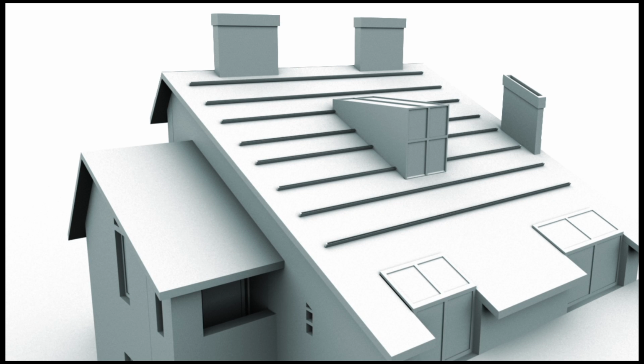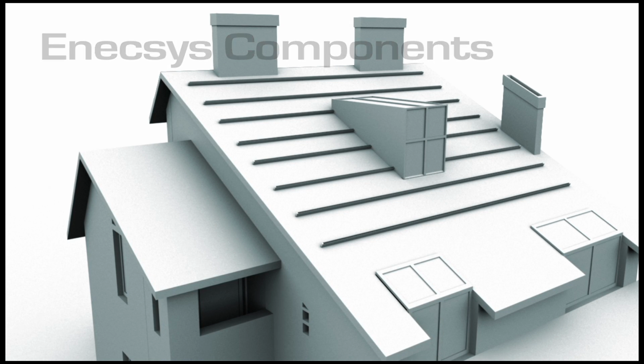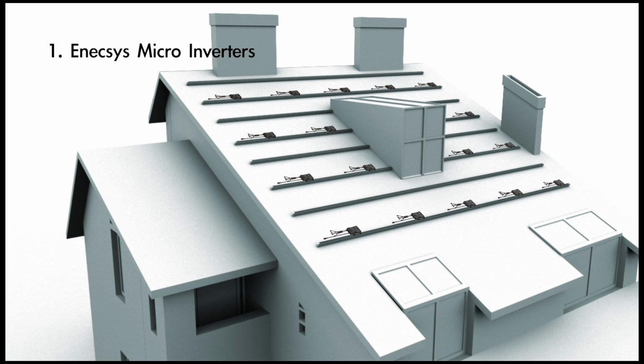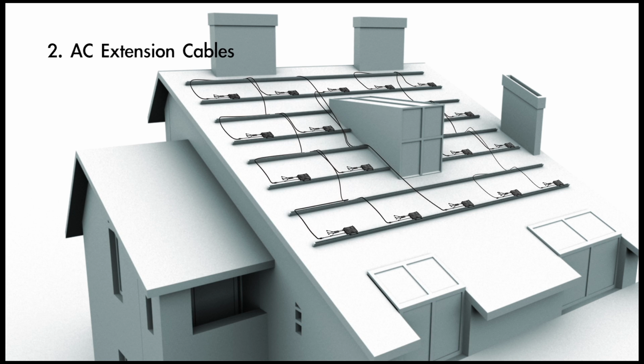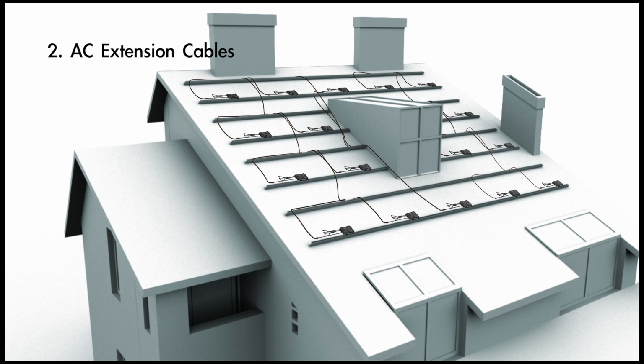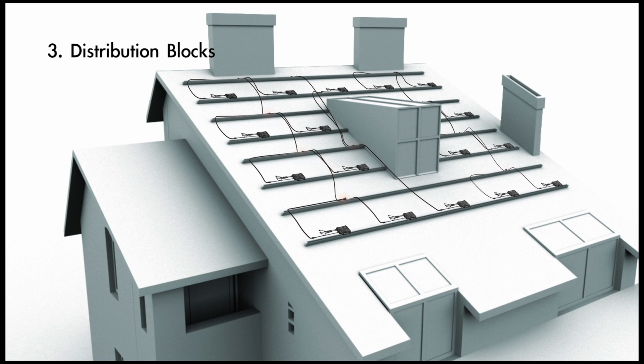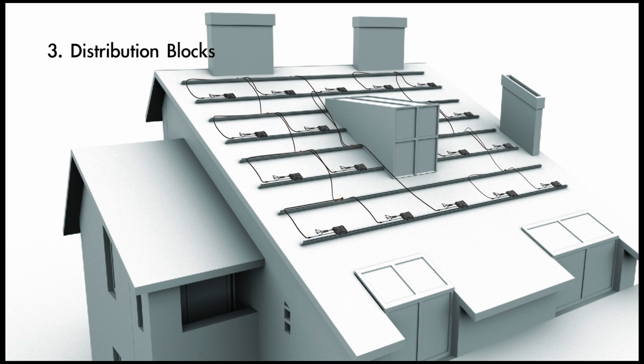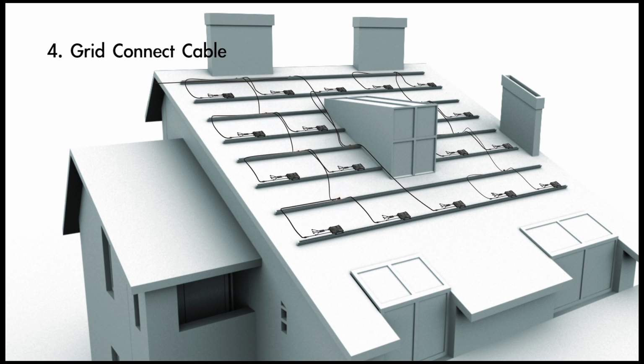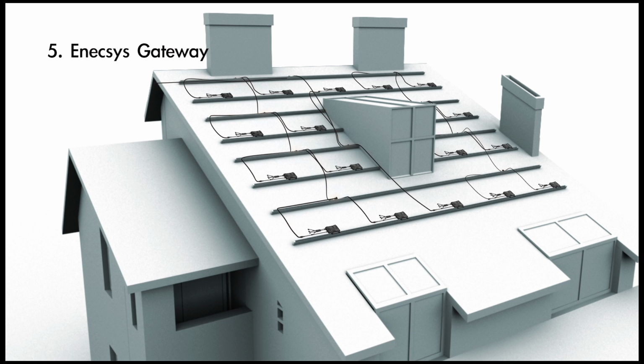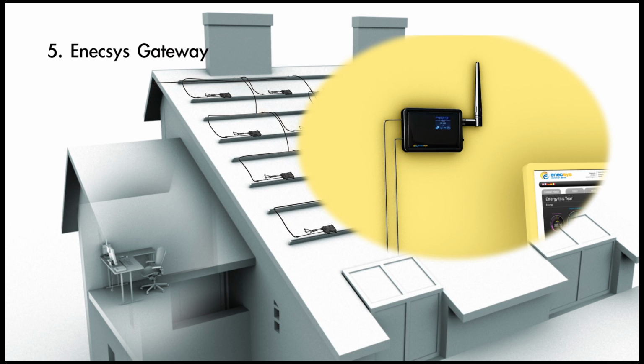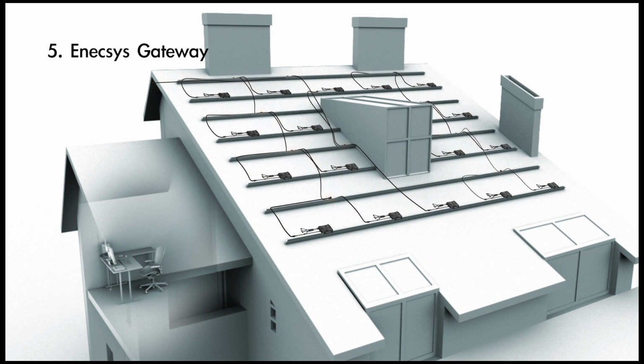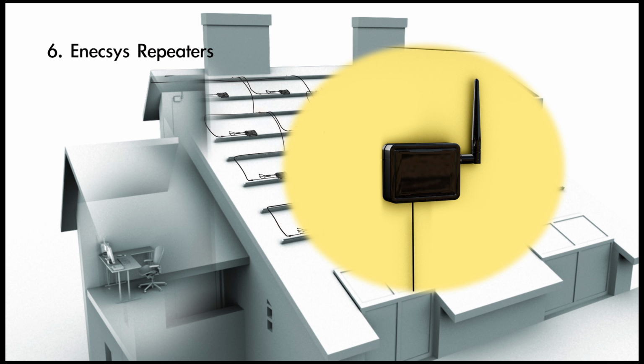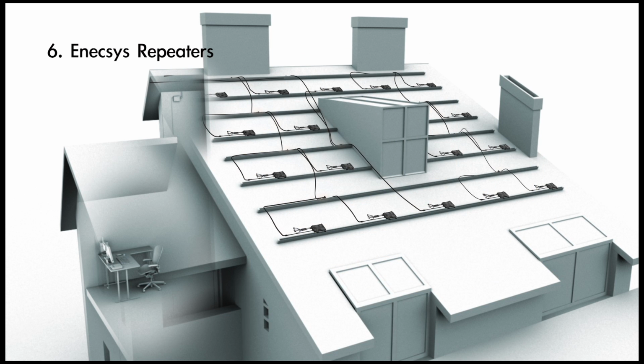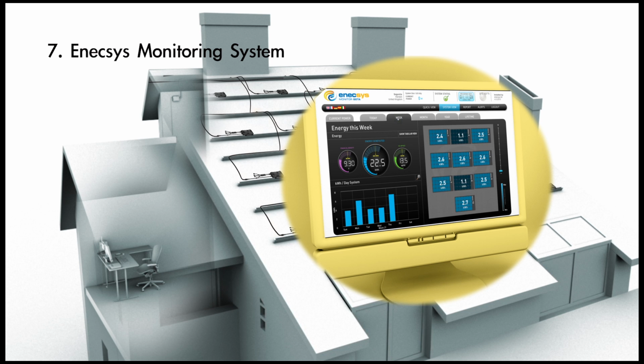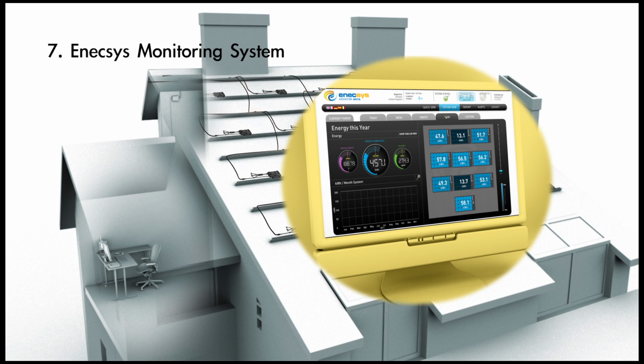The complete Enecsys microinverter system includes the following components. Enecsys microinverters installed on the railing system of the solar modules. AC extension cables used to connect the microinverters to distribution blocks. Distribution blocks to connect the AC chain and join with the grid connect cable. The grid connect cable, which connects the system to the electrical grid. The Enecsys gateway, which transmits detailed performance information from each microinverter to the internet for monitoring. Enecsys repeaters, which can be used to amplify signal strength between the microinverters and the gateway. And the Enecsys monitoring system, where installation performance can be monitored online in real time from anywhere.